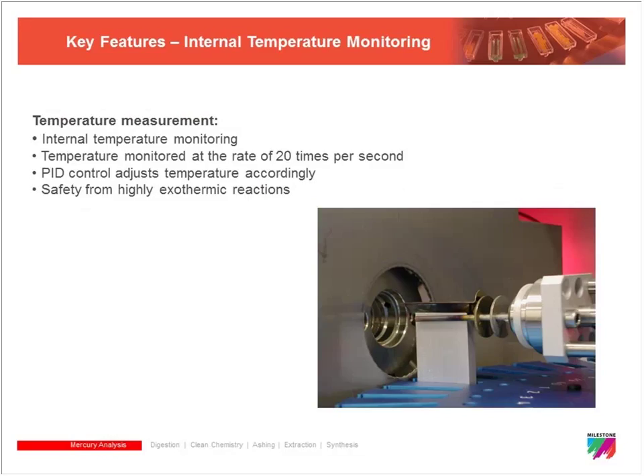Another key feature that the software regulates is the temperature of the decomposition furnace. So there's a thermocouple built into the decomposition furnace that monitors the temperature 20 times a second. So what this allows you to do is run your fatty or oily tissue samples right alongside your dry soils or plant matter, and the decomposition chamber is heated based on the feedback from this temperature monitoring. So in the case of an oily or fatty sample where you may get some burning of the sample inside there, the thermocouple will detect any heat coming from the decomposition itself and slowly regulate that out.